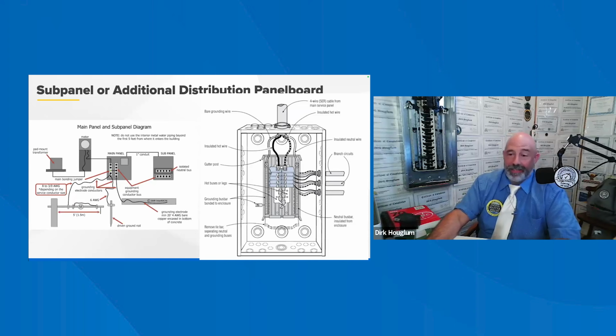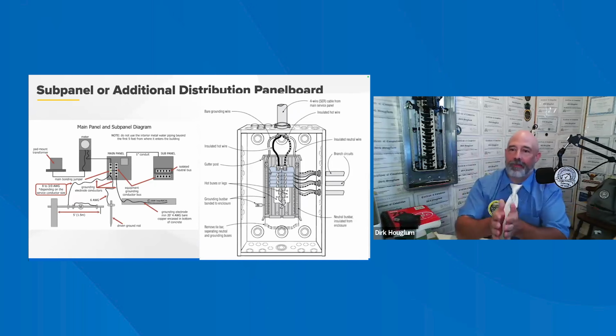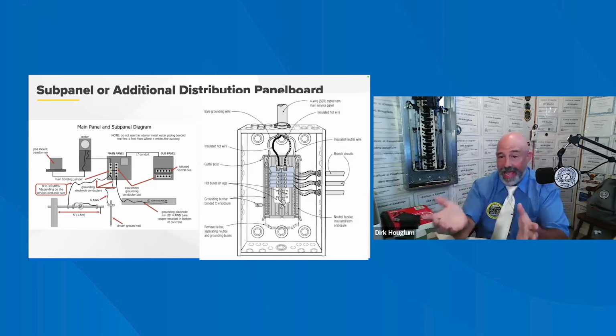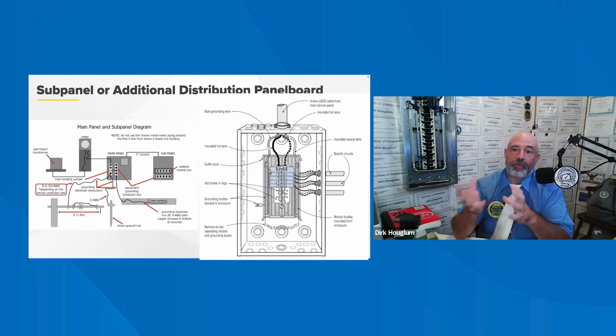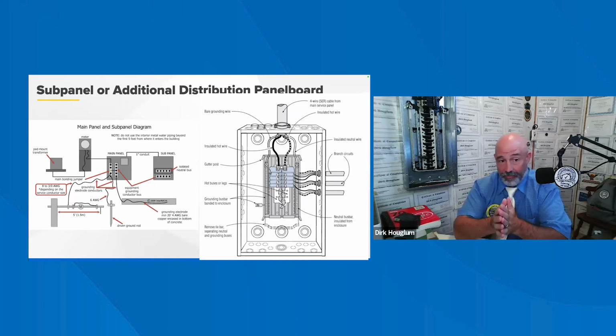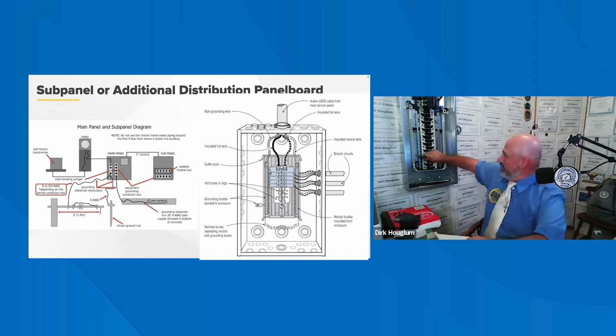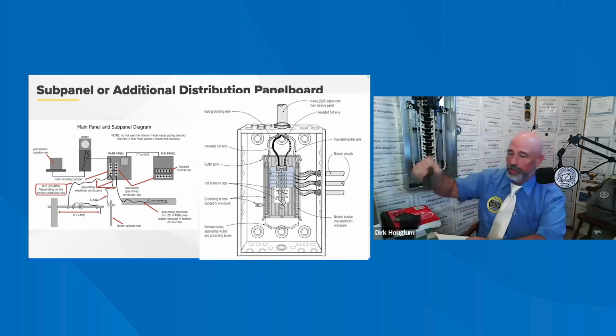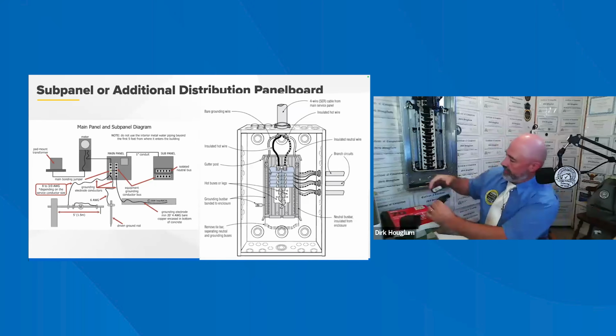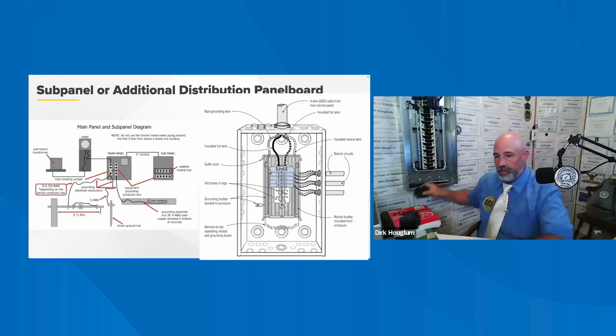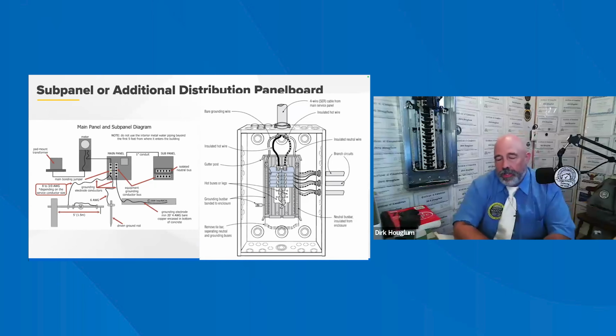Now, a new panel board should not exceed 80% of its full capacity. So if I have a 200 amp, yeah, I won't go there. However, an older panel board may not have room for additional circuits, and sub panels may be added. Sub panels or additional distribution panel boards are typically powered by double pole breakers in main service panels with 4-wire SER feeders. A lot of times you'll see people put in these type of breakers, which we used to call cheaters. You can see the different size, and you can put two side by side together. It can give you a little extra room, but it's not always the right way to do it.